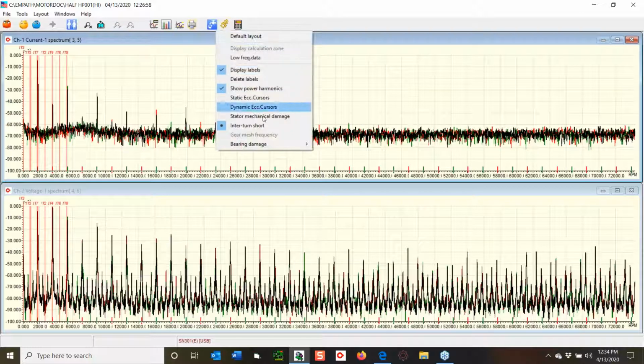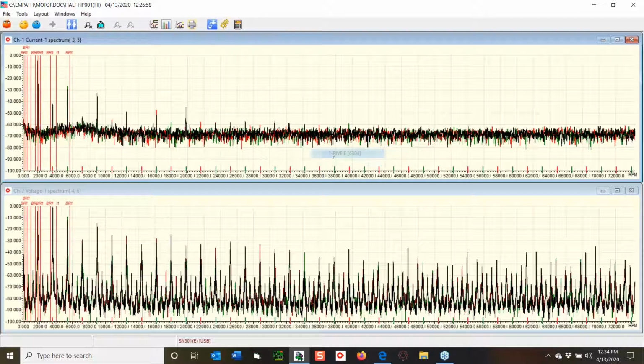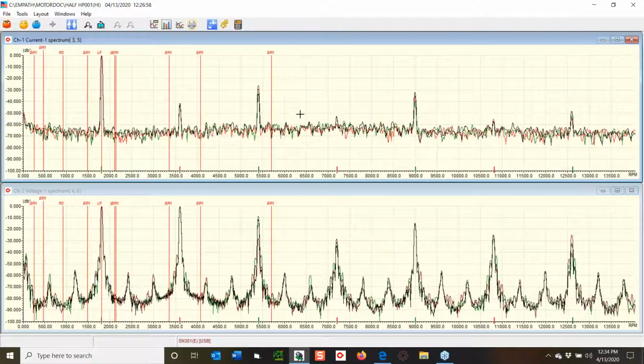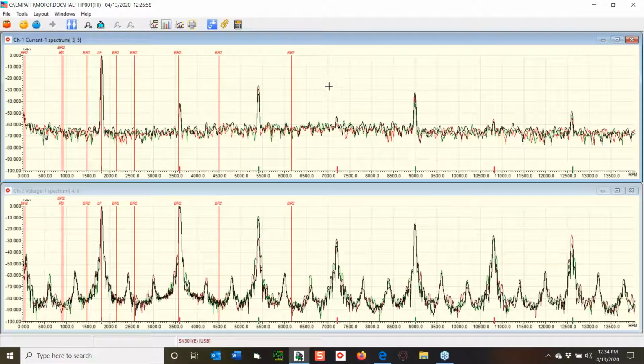But a lot of the defaults, and then of course my bearing stuff — so I come back down here and look to see if I have bearing peaks that were not detected automatically. I like to go in and verify, especially if I'm hunting for a different type of problem. You see, if I come up here, this would be outer race, this would be inner race, this would be — oh, that's the other bearing. Okay, so those are the balls, and so on.